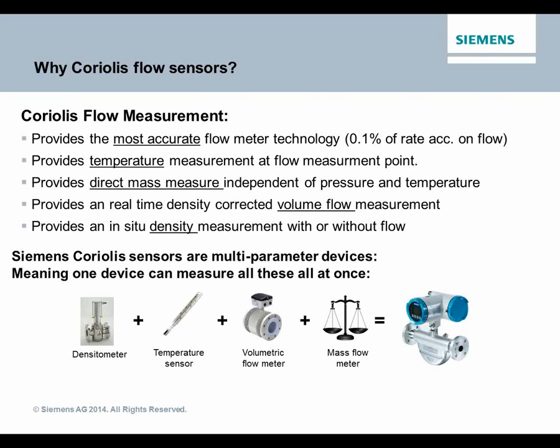Coriolis also provides, and we'll get into this in a bit, a real-time density measurement. And so you can actually tell the density of the fluid in the pipe by the frequency of the tube. The faster the tube vibrates, the lower the density of the material. So you can imagine if there's a flow tube and it's vibrating and it's empty or just has air in it, it'll vibrate much faster than if you filled it with liquid mercury. That would be slow, or it would slow it down because the density of mercury is higher. We'll talk about that. Hopefully you'll be able to hear it in about a slide and a half. If you have questions on it, we'll go through that as well.